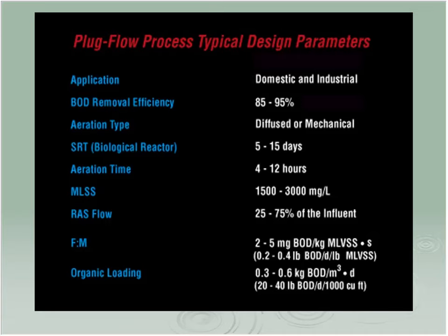If I don't pay attention to what's going on, or if I have some problem with my solids handling and I start moving up into the 15 days, that's where I have to be careful because we're going to start to get into that nitrification process by accident, and that can wreak havoc if you're not doing it on purpose. Aeration time, 4 to 12 hours. Boom, we're done. That's all it takes. Your mixed liquor solids, 1,500 to 3,000 milligrams per liter.